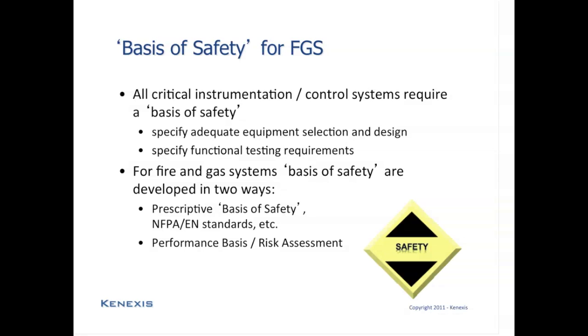Traditionally, for fire and gas systems, there have been two ways that the basis of safety has been defined. The more traditional method is a prescriptive basis of safety. And by prescriptive, we mean that there are standards, such as those standards from the National Fire Protection Association, NFPA, and also European norms that will define what type of equipment you need to install, where you need to install it, and how you need to maintain it. Some of the more common standards would be the National Fire Alarm Code, NFPA 72, and also the equivalent standard in Europe would be European norm EN 54.